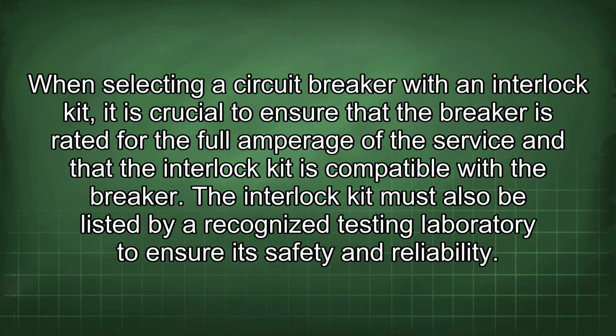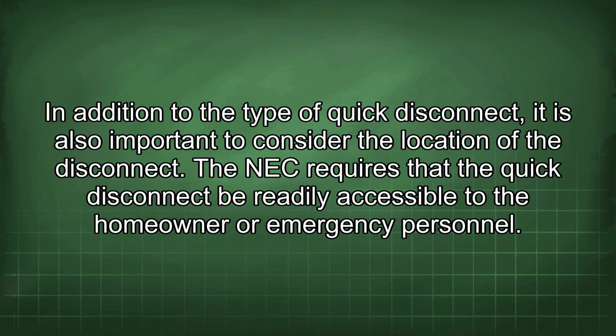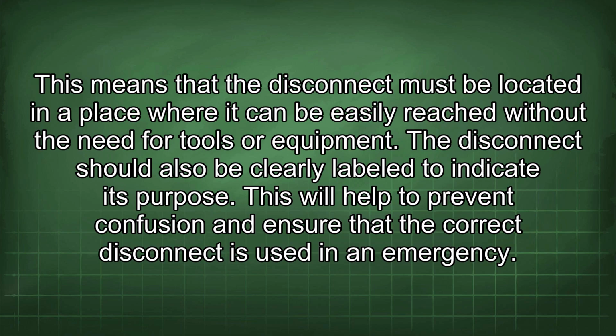When selecting a circuit breaker with an interlock kit, it is crucial to ensure that the breaker is rated for the full amperage of the service and that the interlock kit is compatible with the breaker. The interlock kit must also be listed by a recognized testing laboratory to ensure its safety and reliability. In addition to the type of quick disconnect, it is also important to consider the location of the disconnect. The NEC requires that the quick disconnect be readily accessible to the homeowner or emergency personnel. This means that the disconnect must be located in a place where it can be easily reached without the need for tools or equipment. The disconnect should also be clearly labeled to indicate its purpose. This will help to prevent confusion and ensure that the correct disconnect is used in an emergency.